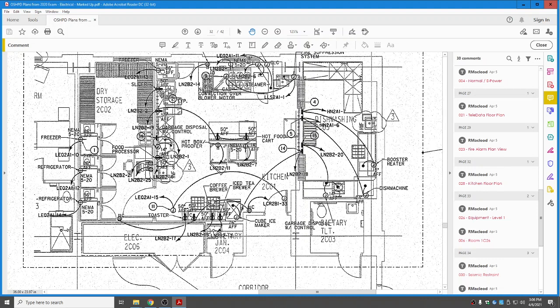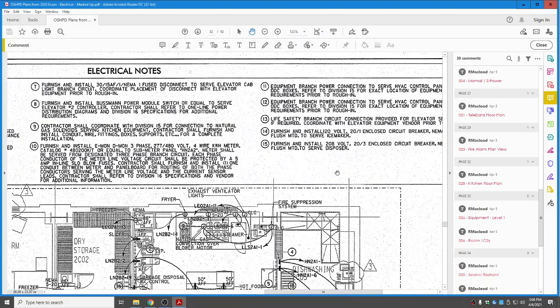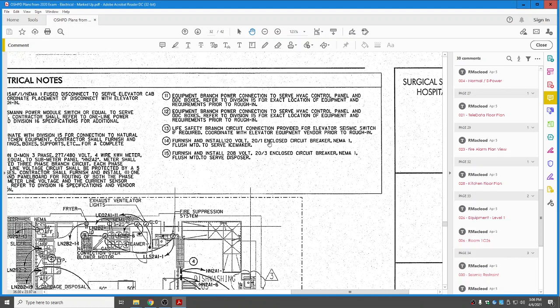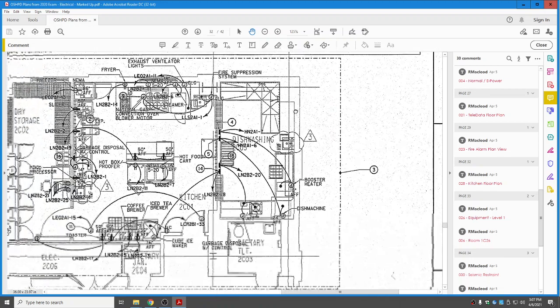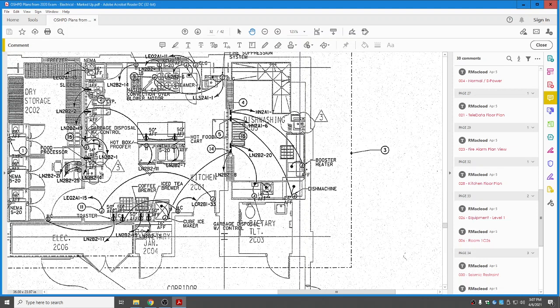Now let's jump over toward the middle of the room. Actually, let's drop to the bottom. You'll see here the coffee brewer and iced tea brewer, and down below it gives you the height of that receptacle off the floor at 50 inches. You have an ice cube maker that's hardwired into the junction box, and that runs over to number 14. Let's take a look at circuit 14 on our drawing. It says furnish and install a 120 volt 20 amp circuit breaker, NEMA 1 enclosure, flush mounted to serve the ice maker. So this is just basically showing you the location, and it's recessed or flush mounted. Okay, I think we've looked at enough here.